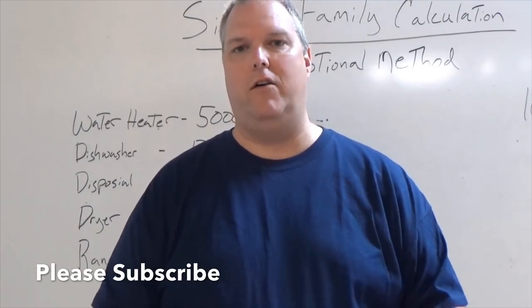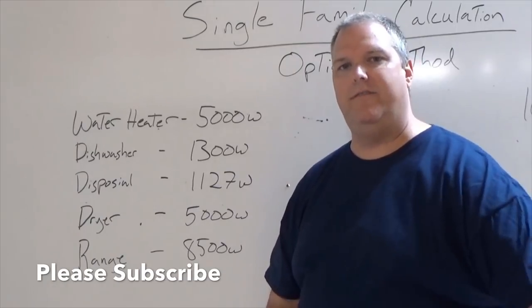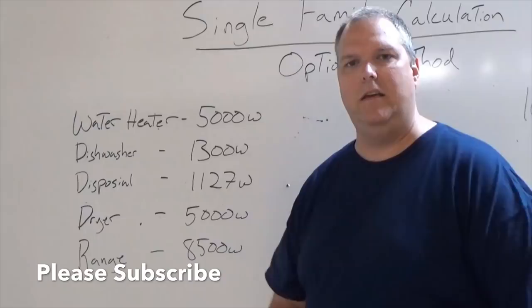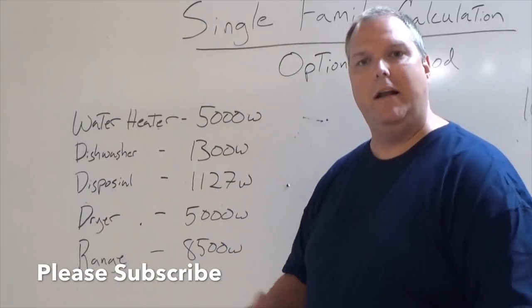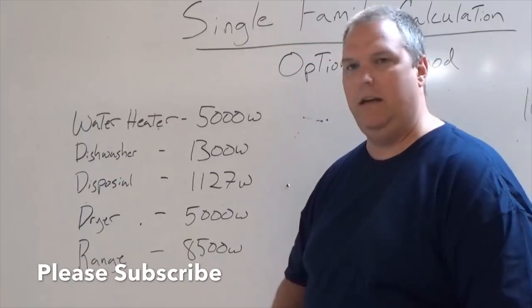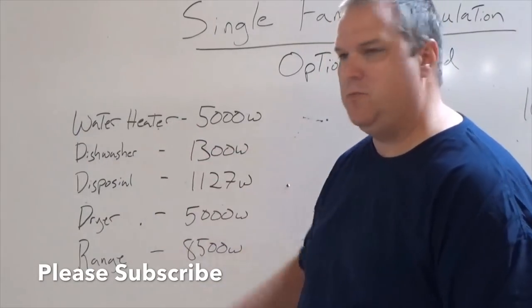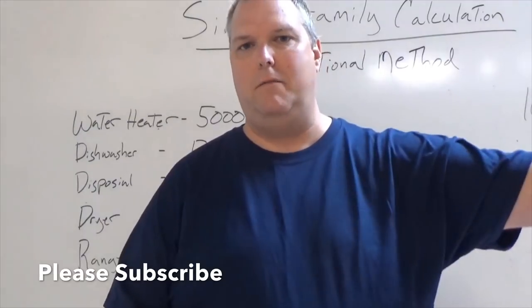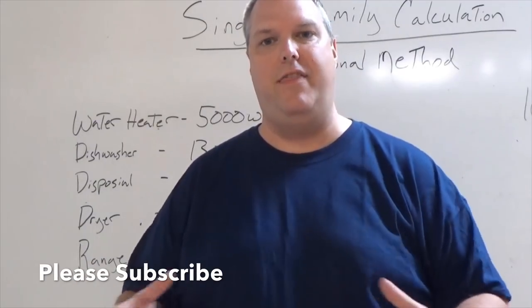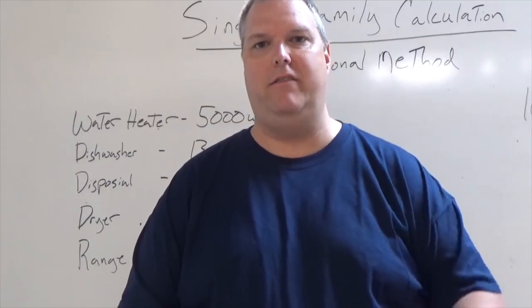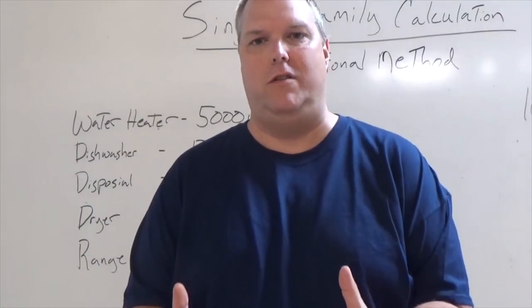You're going to calculate all your fixed appliances — hot water heater, dishwasher, disposal — and find the total wattage or VA. Then, instead of having a separate line for the dryer and range as in the standard method, you're going to add all of this together into this single part of the calculation. In the optional method you add everything into one total.